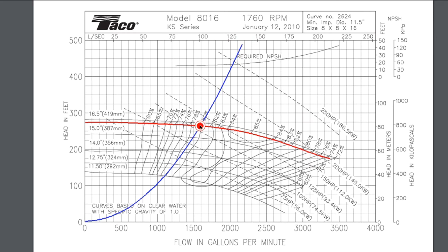At our design flow rate of 100 liters per second, a 16.5 inch impeller gives an output head of about 280 feet. A 15 inch impeller gives only about 235 feet, and a 14 inch impeller in the same casing gives under 200 feet. So I really need to go to a big impeller in this casing to get the head required to drive 100 liters per second — 0.1 cubic meters per second — through the piping.